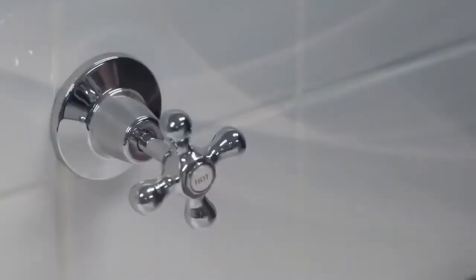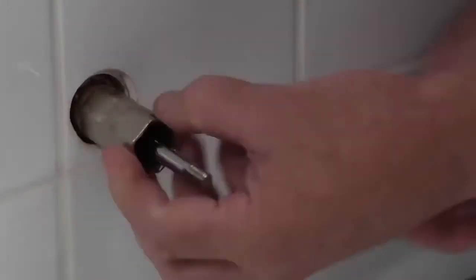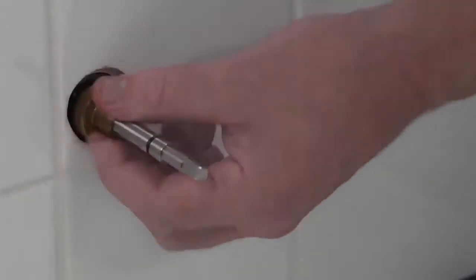The installation of the Maxxis SBA is very simple. Firstly, remove the existing SBAs from the tap bodies. If the seats are damaged and need to be reseated, please do so by using the patented Ewing shortcut tap reseater. Once any of the foreign matter has been removed and the seat is smooth, it is time to install the Maxxis SBAs.